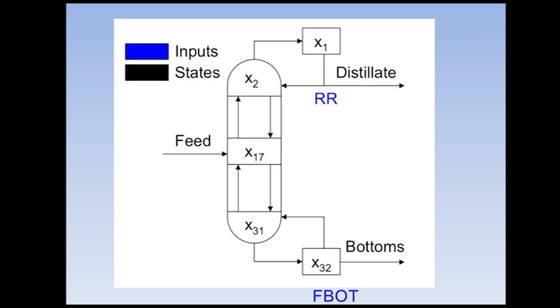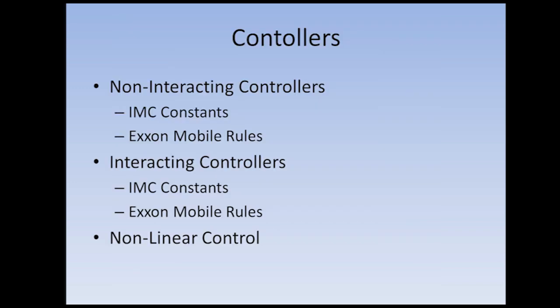So here we have a diagram of the distillation column model that we were using. We ran a few step tests on our distillation column to find some different tuning constants for our controller. We would change the reflux ratio and measure the distillate change, the fraction of the feed going through the bottoms and the bottoms change, as well as the feed as a disturbance and measure how it affected both of those. Once we had our Kp, ThetaP, and TauP, we would use some rules to turn them into tuning constants.